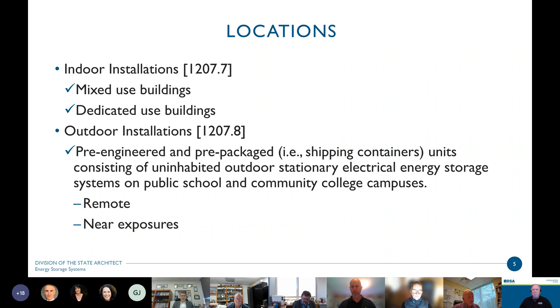So we get into Chapter 12 of Title 24, Part 9, but also many of the articles within Title 24, Part 3, the California Electrical Code, contain requirements designers need to follow. NFPA 855 is a nationally recognized standard. However, if you check Chapter 80 of the Fire Code, you'll note that the Office of the State Fire Marshal doesn't necessarily adopt this standard specifically. Primarily that's because with the reformatting of Section 1207 in the 2022 code, many of those requirements were, during the development process a few years ago, coordinated with 855 and the revisions to UL standard 9540. So if any of you care to go through 855 and compare it to section 1207, you'll find the requirements are extremely similar.